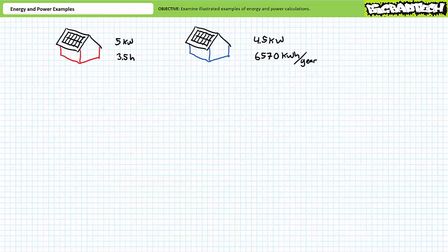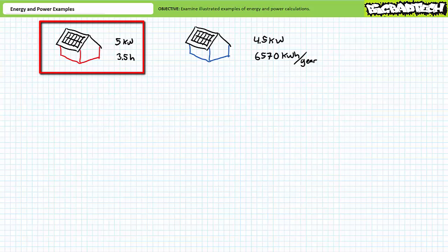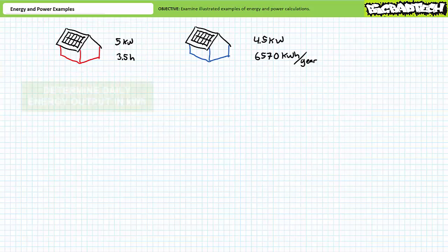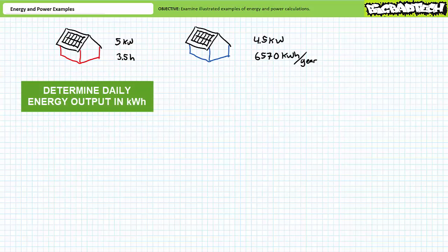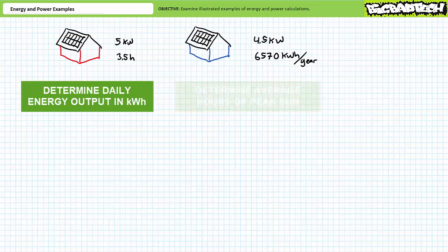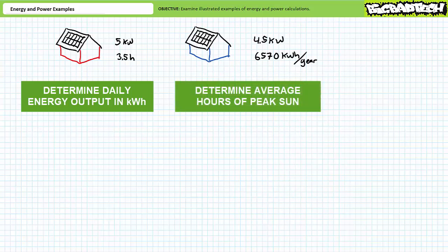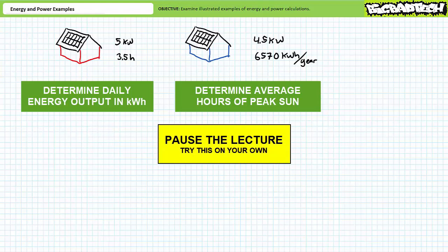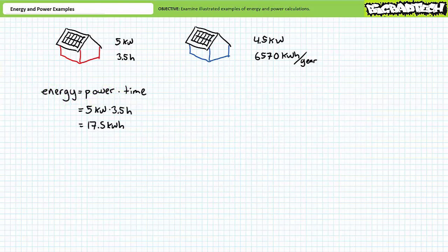Let's put your understanding of peak sun hours to the test. Consider a five kilowatt array installed in an area known to regularly experience 3.5 hours of peak sun each day. Determine how much energy this array will produce each day on average. Energy is power times time: five kilowatts times 3.5 hours yields an average daily energy output of 17.5 kilowatt hours.